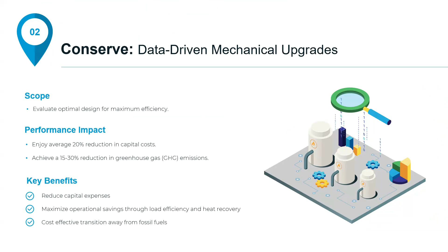Now you're getting so much more data. In the case of these buildings, if we think about multi-res buildings, which are generally considered simpler mechanically than most commercial buildings, now we're getting real-time data from every thermostat in the building. That's something that's traditionally never been available within a multi-residential portfolio. Typically, the controls, or at least the visibility into the operation of the building, never extended beyond the mechanical plant in multi-res. Now we have full visibility, not just in the plant, but in every suite, the lobby, the stairwells, and the mechanical room, including its temperature. All of that data is now available in real time.